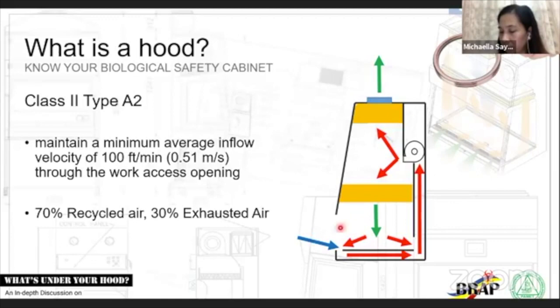Check if they are EN12469 or they are NSF49 certified. So if you're class 2 A2, again, clean air goes in. Now your blower is up here. It creates now a vacuum in this space. So there is a vacuum. There is no positive pressure, dirty air. Okay, so there's a vacuum here.